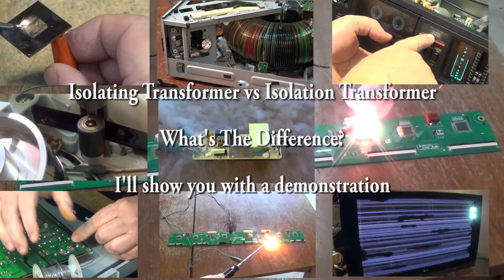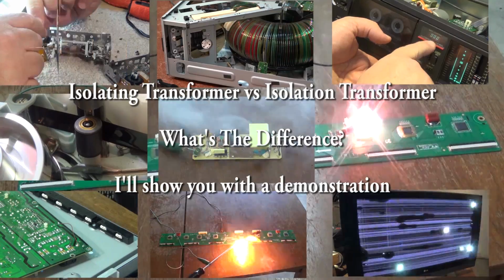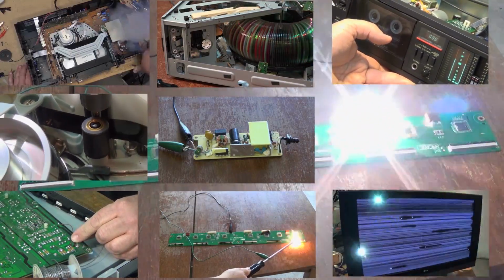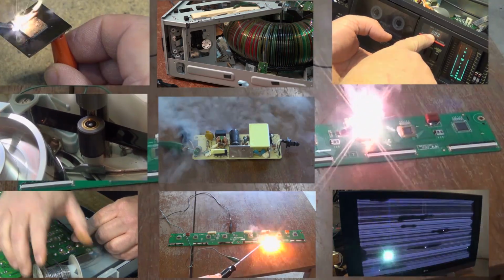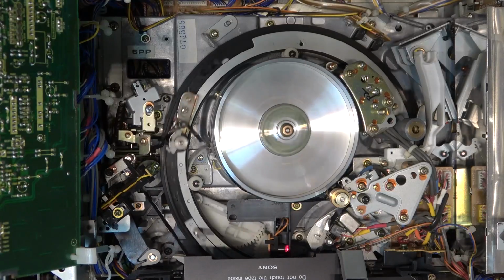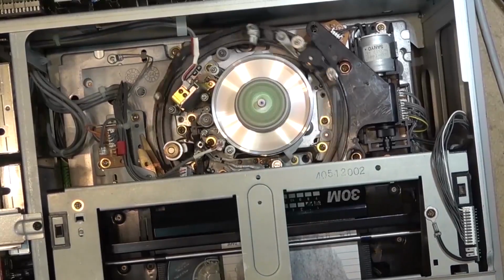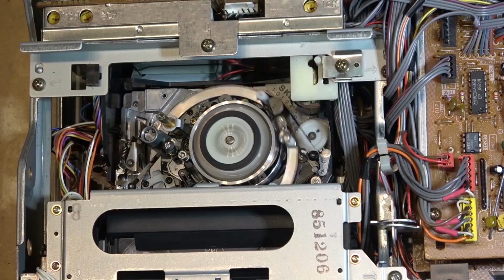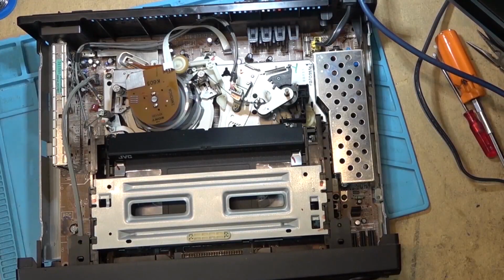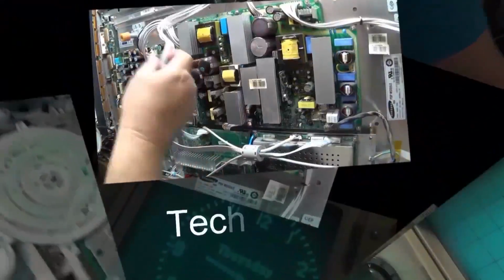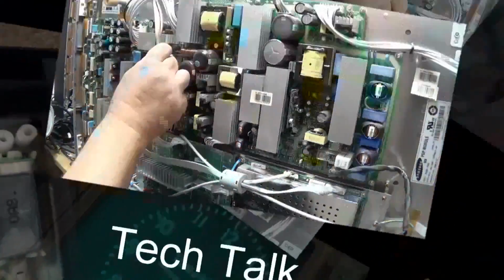Isolation versus isolating. What's the difference? When you're talking transformers, there's a huge difference between an isolation transformer and one that is just isolating. I'm going to try to explain the differences here, and I'll show you guys with the meter some test results to prove the difference between the two different setups. I only have one here, but I can simulate the other. Let's check it out.